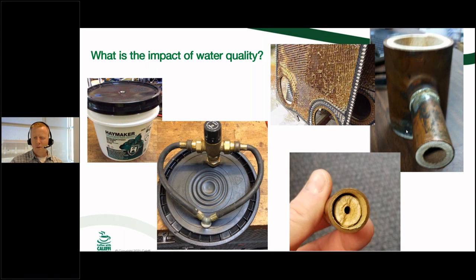I believe it was a 3 or 4 inch T. And again, your brazed plate or your plate and frame type heat exchangers, they're going to scale up like crazy. So if you've got hard water, don't think that your mixing valve is not going to need attention. This is something that needs to be managed, and putting it into the preventative maintenance schedule is going to be the best bet for you and your customers.